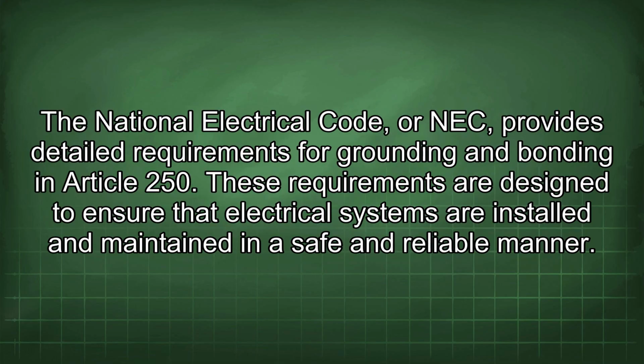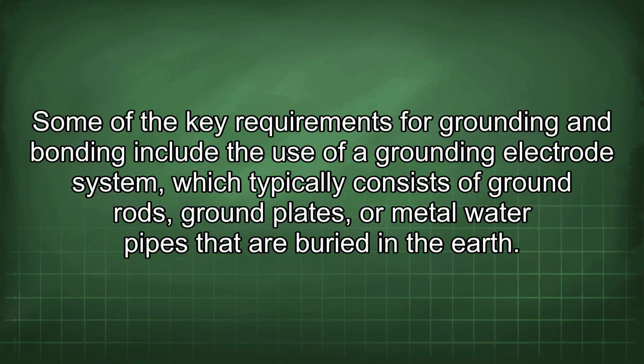The National Electrical Code, or NEC, provides detailed requirements for grounding and bonding in Article 250. These requirements are designed to ensure that electrical systems are installed and maintained in a safe and reliable manner. Some of the key requirements for grounding and bonding include the use of a grounding electrode system, which typically consists of ground rods, ground plates, or metal water pipes that are buried in the earth.